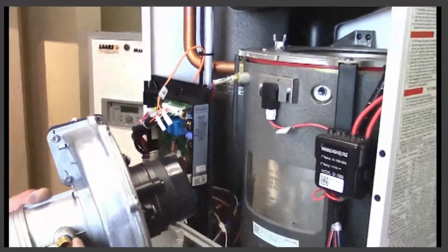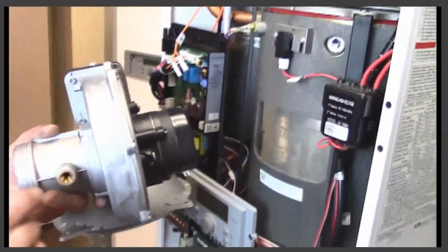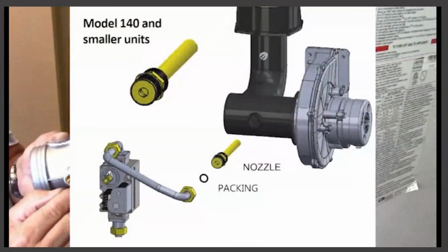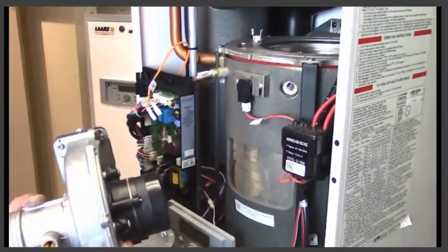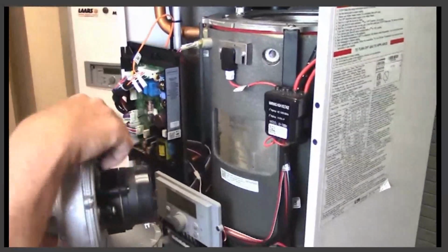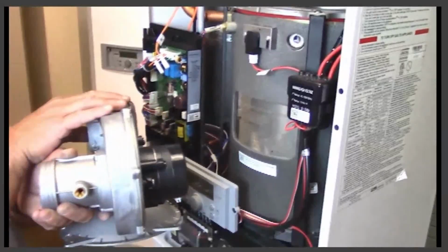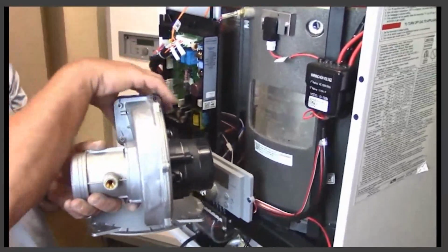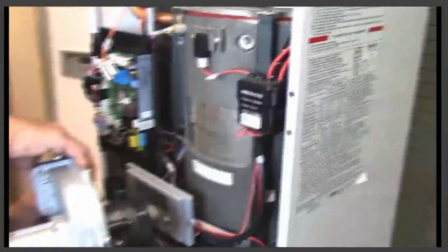And again, this is a 199. It has a smaller orifice. The 140 and smaller boilers will have a threaded orifice into a plastic housing. Be careful that you don't break that if you're trying to tighten that. On the 140, you do not need to remove the orifice from the venturi.